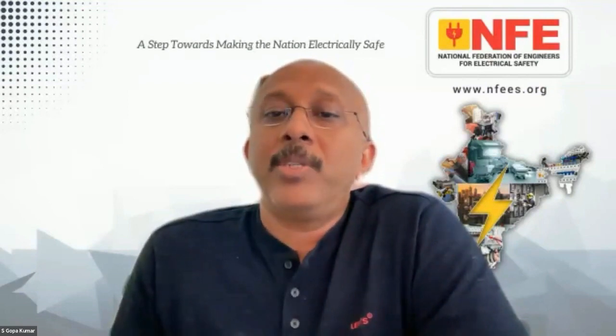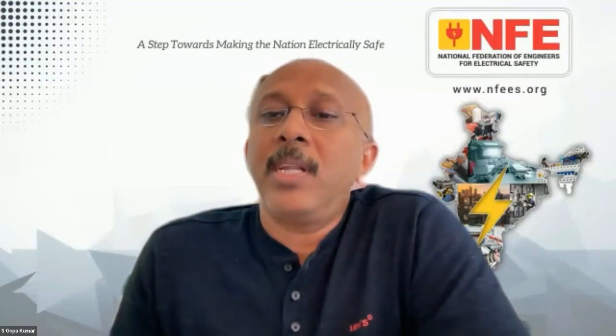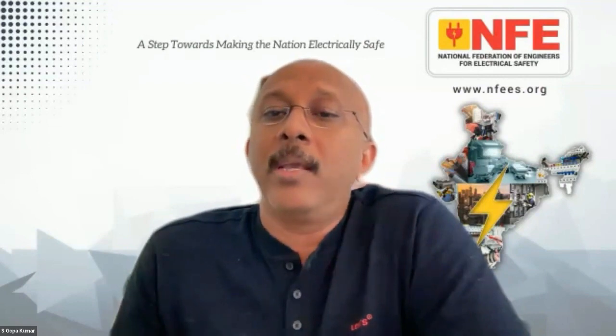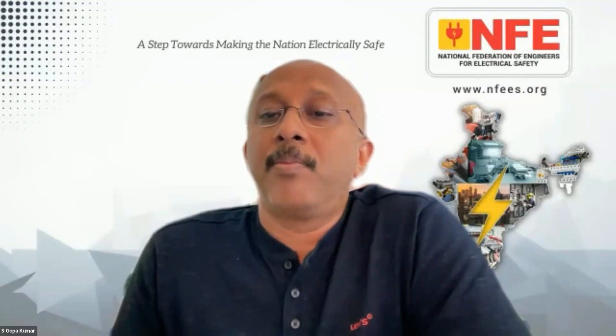So there is a question from Mr. Amritlal. The public network of residential small commercial installation, the supply is by TNS or TNC in UK for new network. Well, TNC generally is frowned upon. TNC actually refers to the supply distribution anyway. So when you have a TNCS, it's separate within the installation, because there's a bit of double standards with this. So TNC is not permitted within a fixed installation, but then the regs also say you can use it, but you have to meet a whole load of other criteria because it's deemed quite dangerous within an installation. It's always worth separating the neutral and earth.